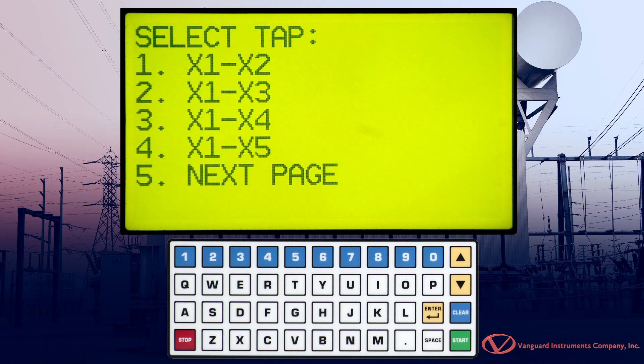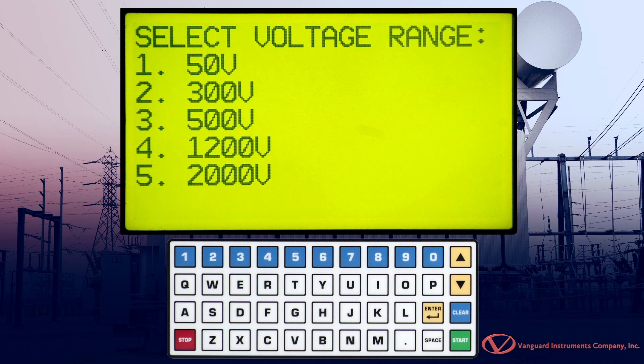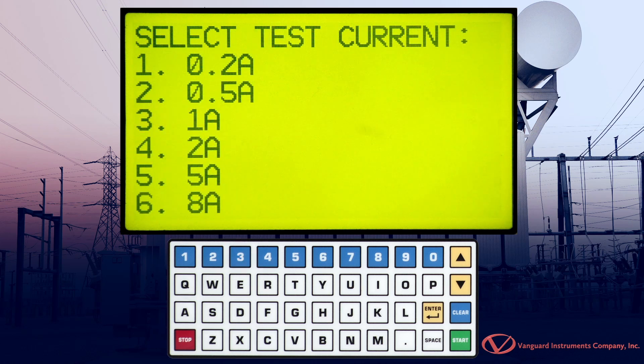Next, select the tap connection by pressing the corresponding key. For this example, we are using tap X1 to X2, so we'll press the 1 key. From this screen, we'll select the test voltage. Press the 3 key for 500 volts.